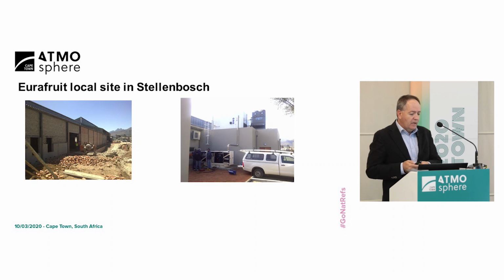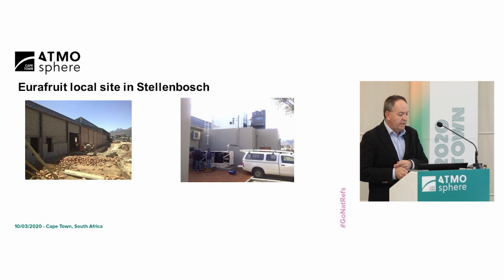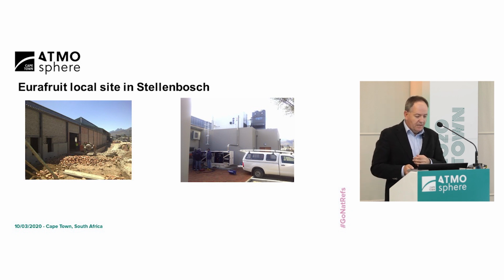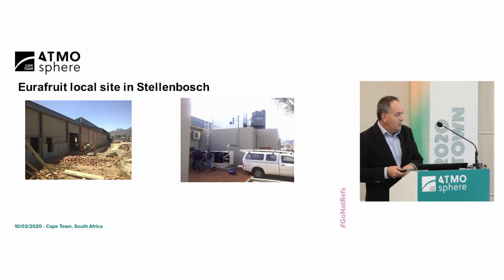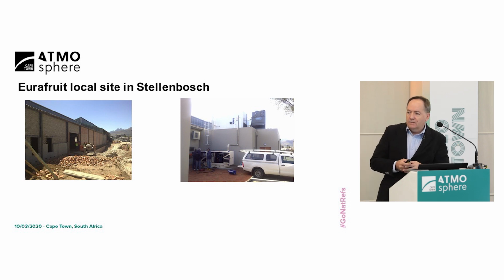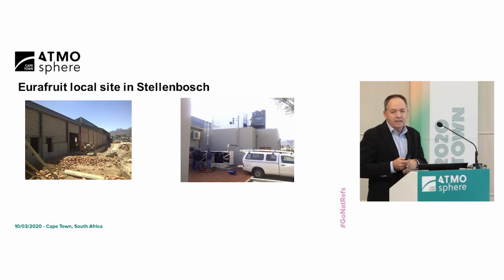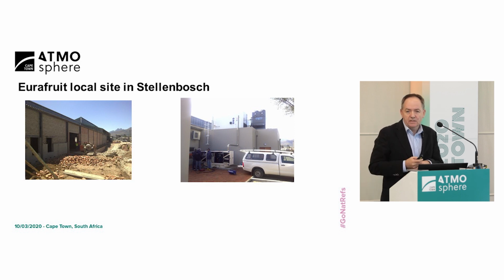This is the site where, basically, we customized the solution for the client. This was his site in the process of being built, and basically that's a similar view. So we placed the plant on top there. Sorry, the picture maybe isn't very clear, but the plant room is on top there. You can see the evaporative condenser at the bottom. So if you had a leak, and the likelihood of the southeaster blowing there is very good, if you had a leak in that plant room, it would all just blow away at such a rapid rate. So that's the safest location we could possibly locate the plant room at.